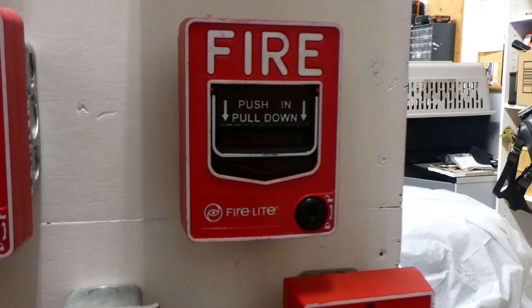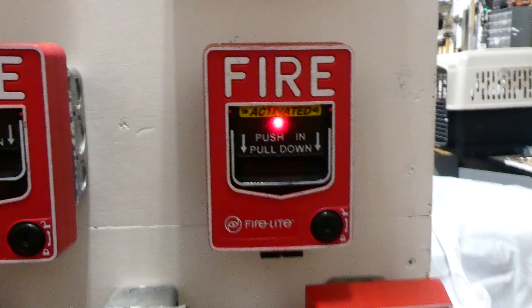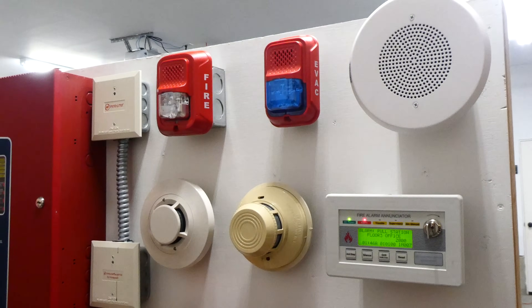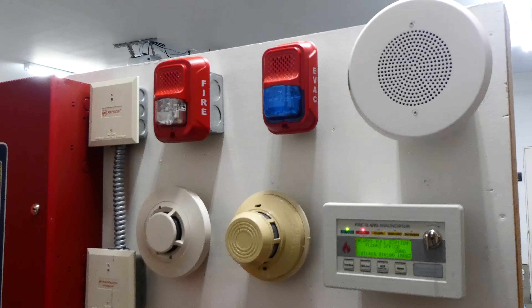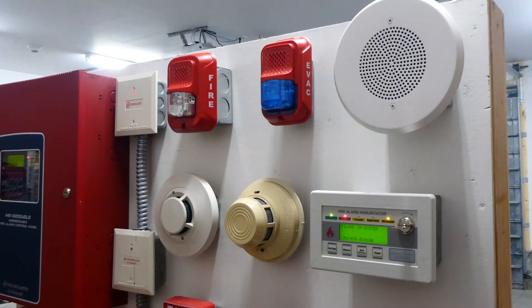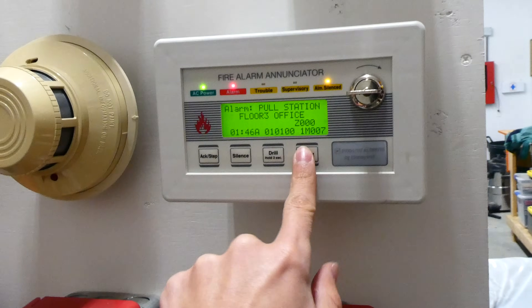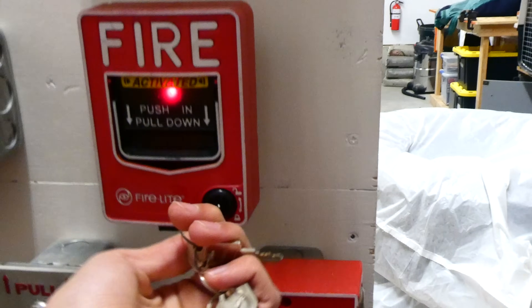So we can't do a system test without pulling something, so we'll go ahead and pull this Fire-Lite BG-12LX. May I have your attention please, a fire emergency has been reported in the building, while this is being verified please leave the building by the nearest exit, do not use the elevators. We can go ahead and reset the annunciator which will reset the main control panel — the system takes about a minute to reset — and we also can't forget to reset the fire alarm pull station.